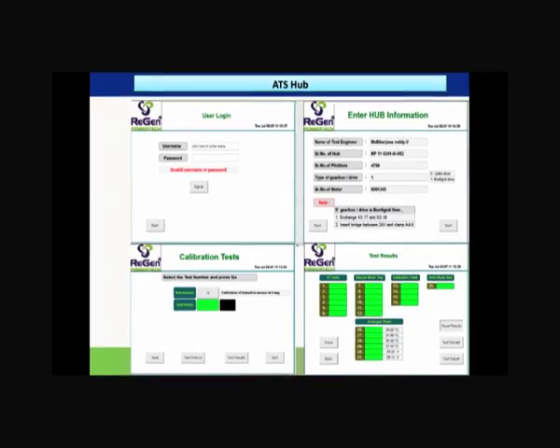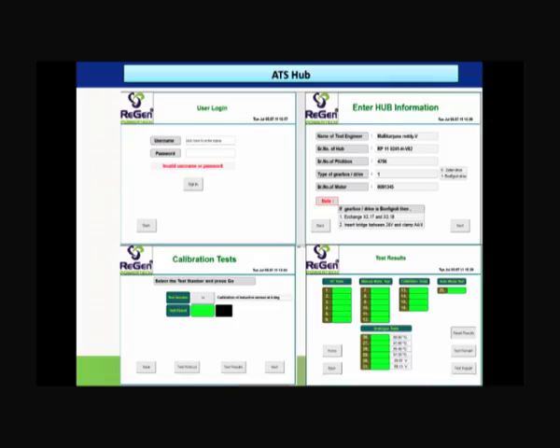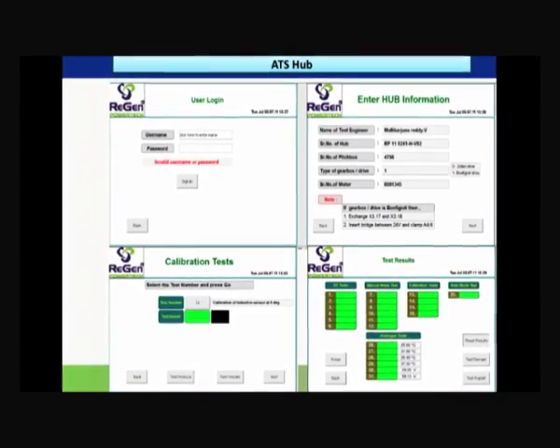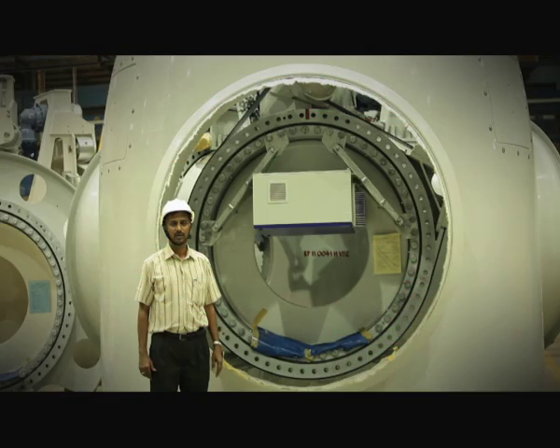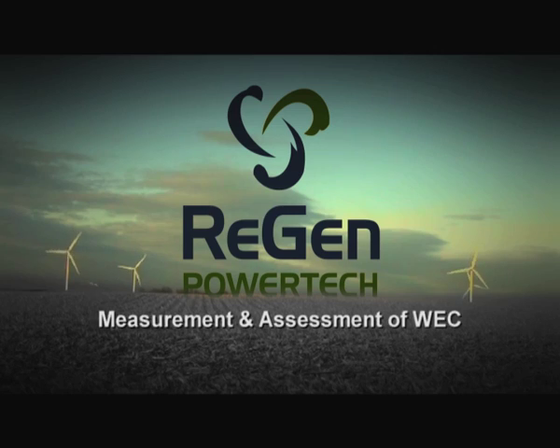This is the ATS, Automatic Test System, which is for nacelle, hub and converter testing. The advantage of this testing equipment is that it is fully automated, and a fully automated report is generated through this system. It has been developed by Regen engineers and established locally.